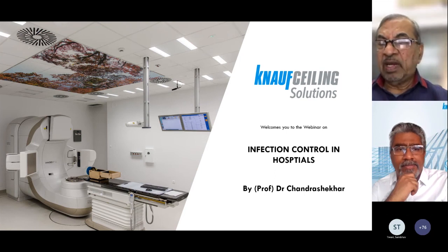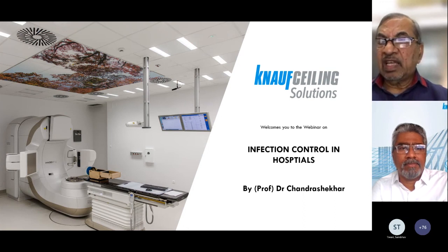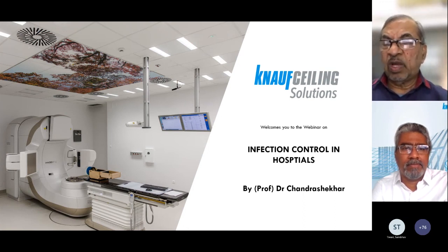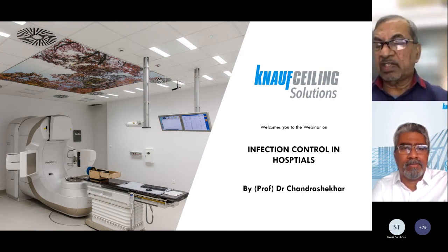So what is needed? We put one exhaust in the system and a crisis button, or alert button, at the nurse's duty station. When something happens, the nurse presses the button and the exhaust system starts working. But the nurse is busy—she may push the button and go away, and outside 45-degree temperature may get inside. So you use a damper so that once the air volume has gone, it comes back to normalcy.